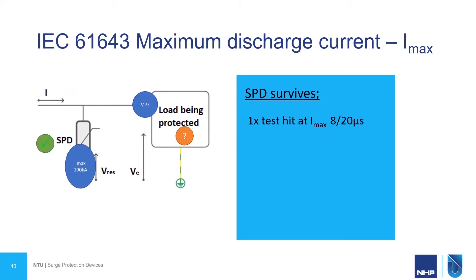IMAX is the maximum discharge current. This is the largest one-time test current that an SPD can survive. It's always a lot larger than the nominal current because this time it only needs to survive one hit, whereas nominal current needs to survive 15 hits. Note that while it's a good gauge to compare between different SPDs, it doesn't actually tell us anything about our protection of our load, because the residual voltage will be higher than UP, the voltage protection level.